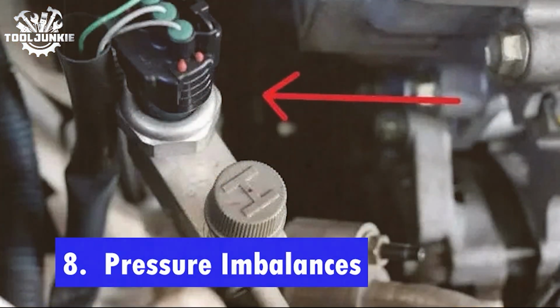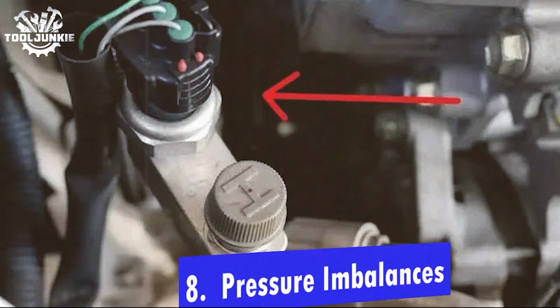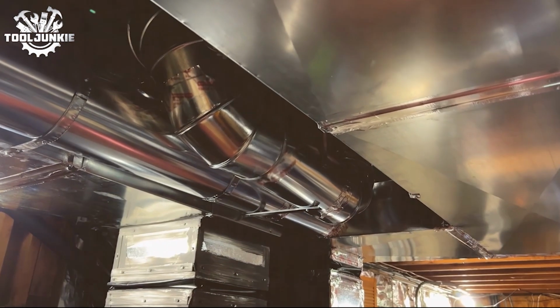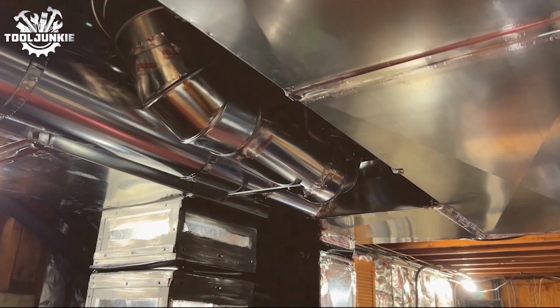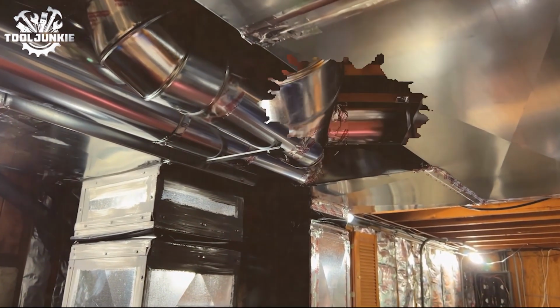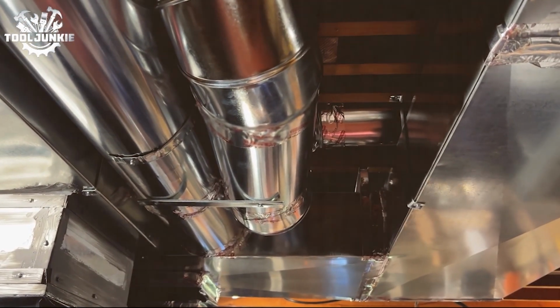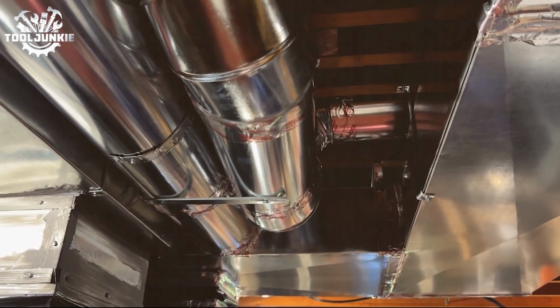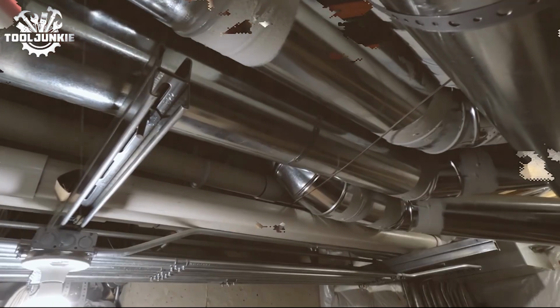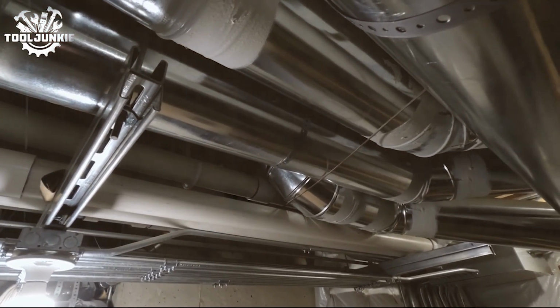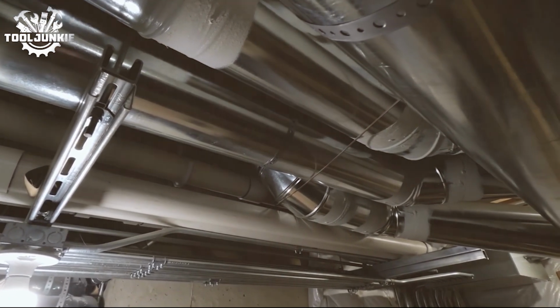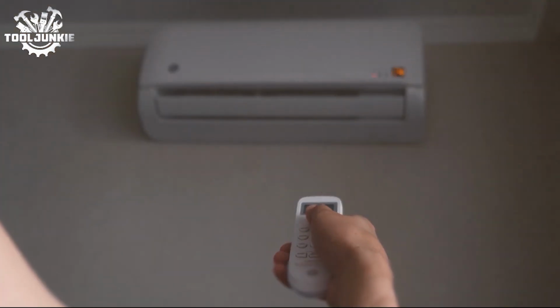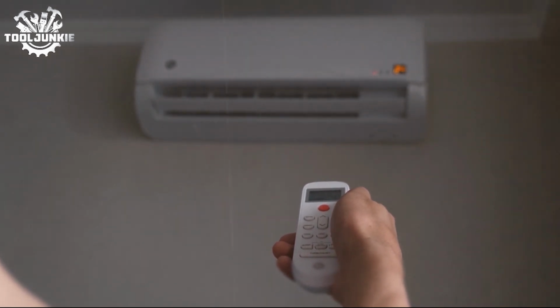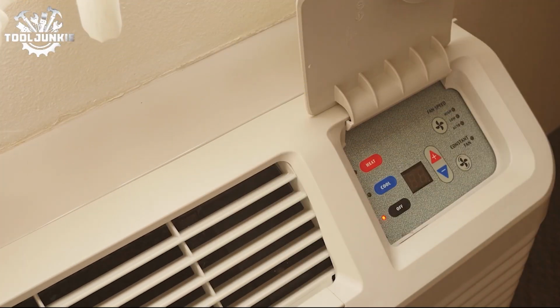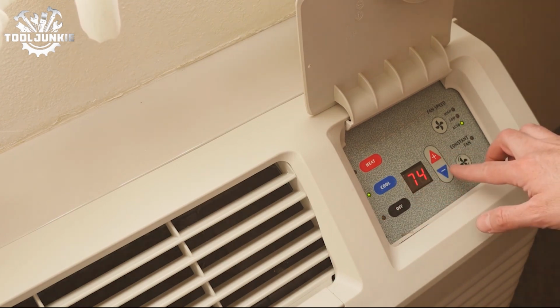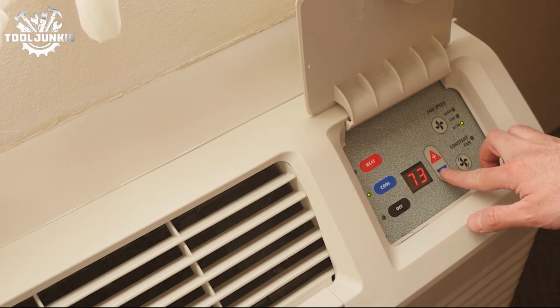Last but not the least problem, pressure imbalances. Pressure imbalances in your home can also lead to short cycling. If the pressure is too high inside your home, it can push the cool air out, causing your system to turn off too soon. Conversely, too low pressure can draw hot air in, making your AC work overtime. What's the expert advice for this? Balancing the pressure involves proper ventilation and sometimes adding or adjusting exhaust fans. It's a nuanced issue, but addressing it can stabilize your AC's operation.